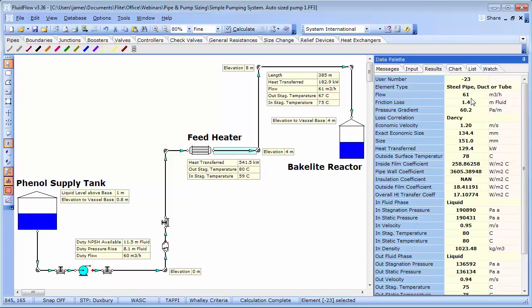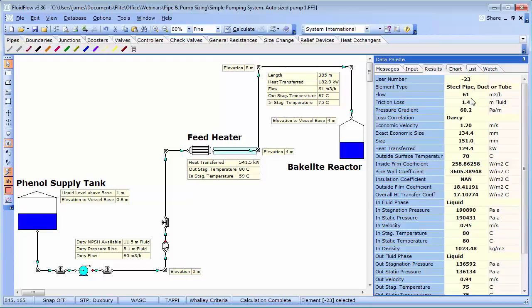Can we experience transients? Our recommendation is always leave the pump selection to the pump supplier who will consider many factors such as, correct selection of pump build materials, adjustment of water-based NPSH curves for the temperature and fluid you are pumping to ensure no cavitation will occur, ensure that the duty point is near the best efficiency point, correct the pump performance curves for any viscosity effects, and so on.